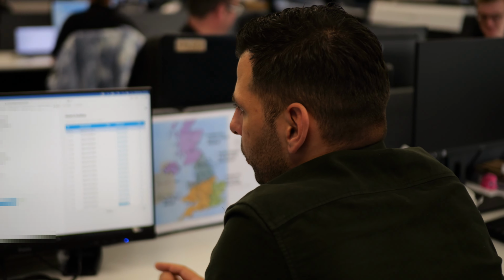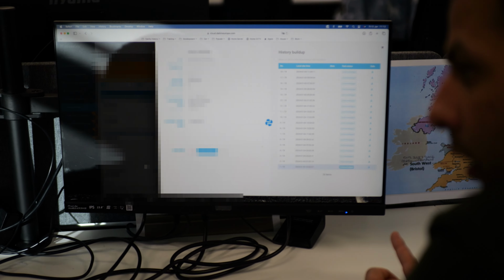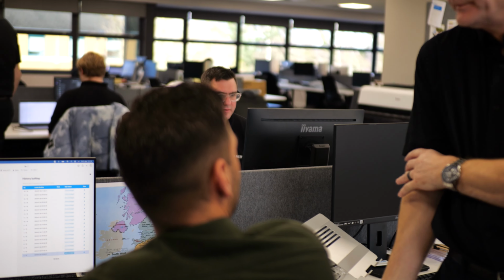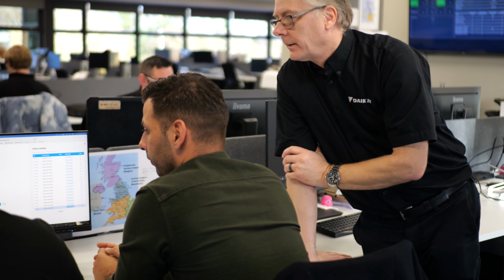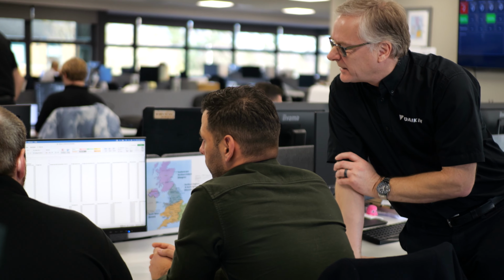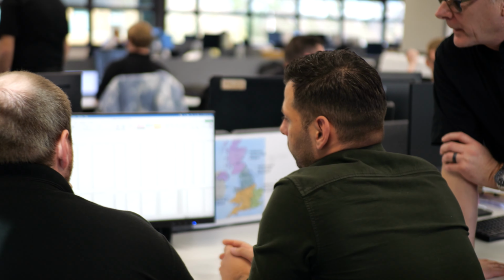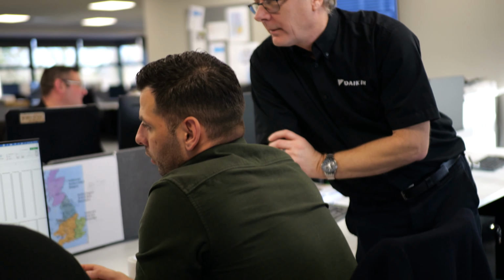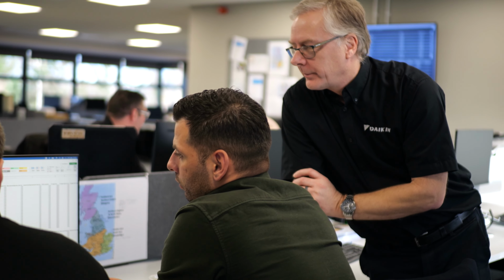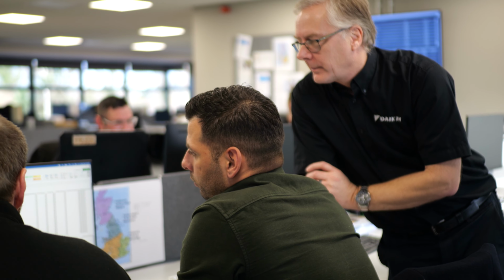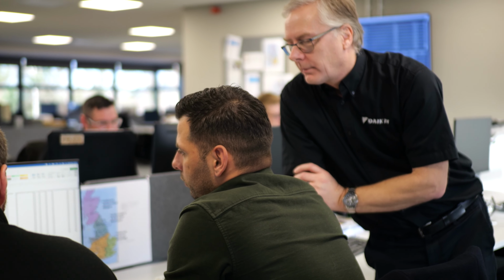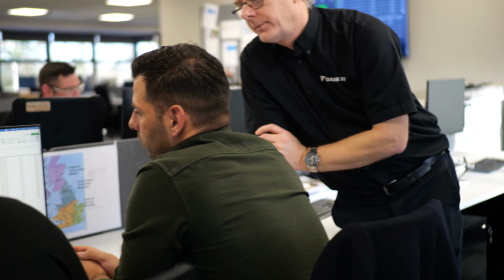Does this data give you, like we said earlier with the service checker, that much information? Yes. Wow. So this is where we're talking about the data dump. It gives you the full data before it went into fault. So that's the previous half hour's worth of running data. You can see this is the outdoor information. So it's P3 prior to that, and then an L1 for some strange reason. But it will give you all of the information: pressures, temperatures, what's actually happening, what's the operation. What's the P3 fault code?